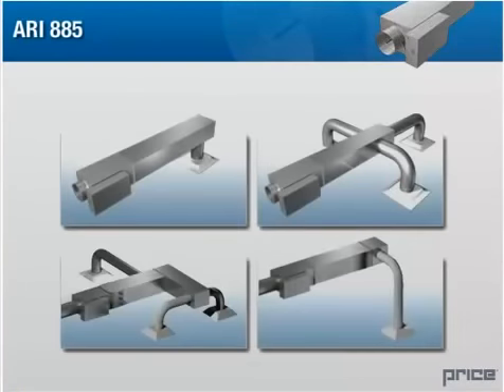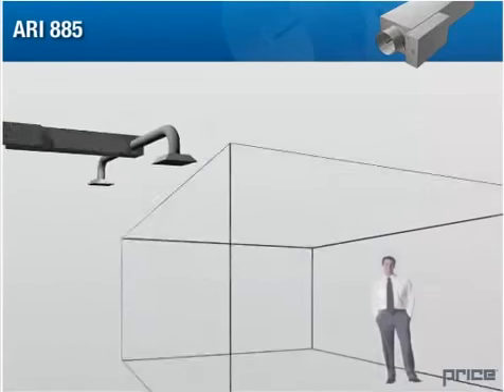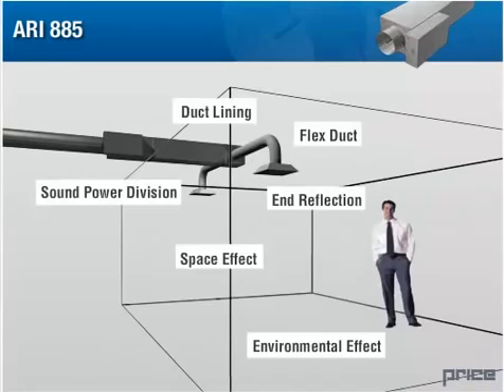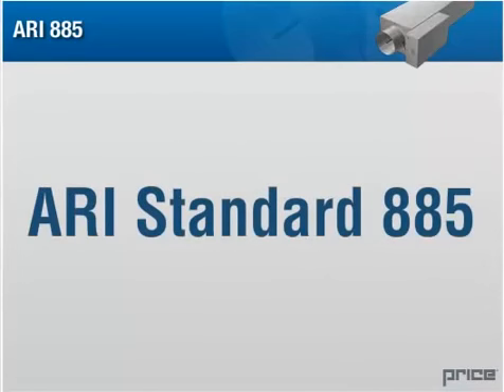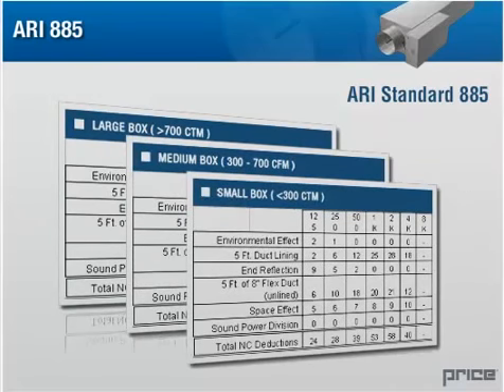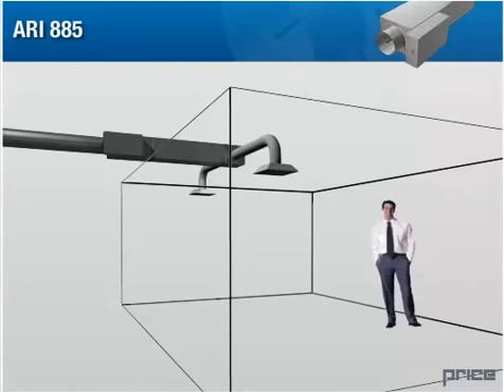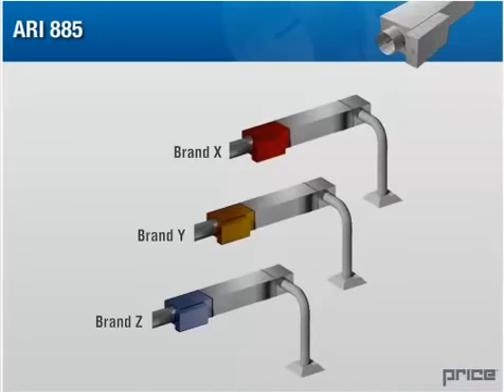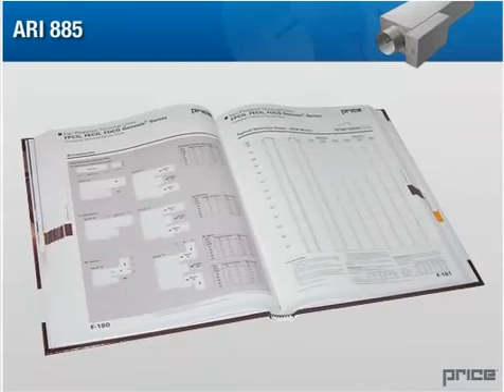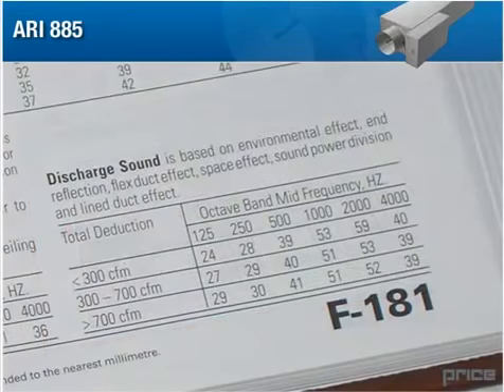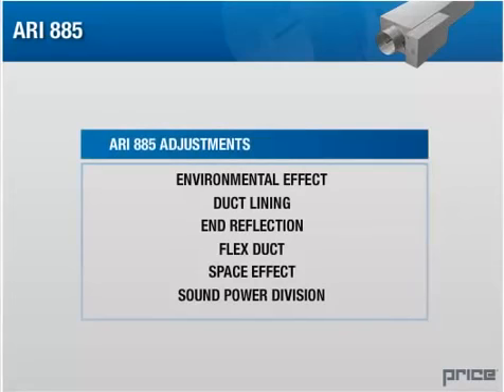Since these products can be used in a wide variety of applications, we must make certain assumptions postulating what effects various duct elements, air outlets, and room characteristics will have on the sound performance. ARI 885 describes a set of typical installation conditions and the attenuation effects that each will have on the noise produced by the terminal unit. These adjusted figures provide an estimate of the amount of discharge noise that will be perceived in the room and provides a basis of comparison between different products. You will see these attenuation values or assumptions printed at the bottom of most reputable manufacturers' catalog data sheets and labeled as a sound power deduction. ARI 885 gives attenuation values to allow for the following effects.